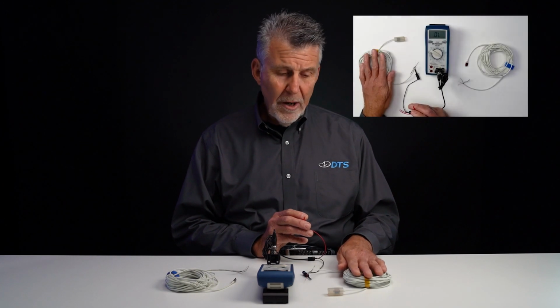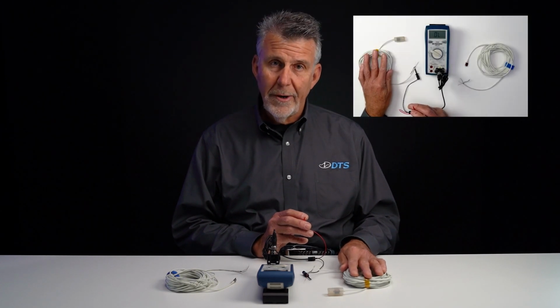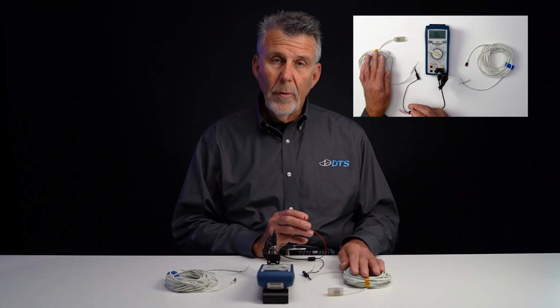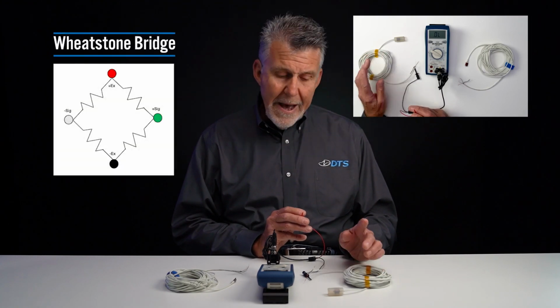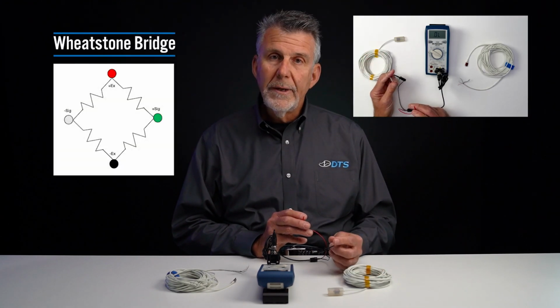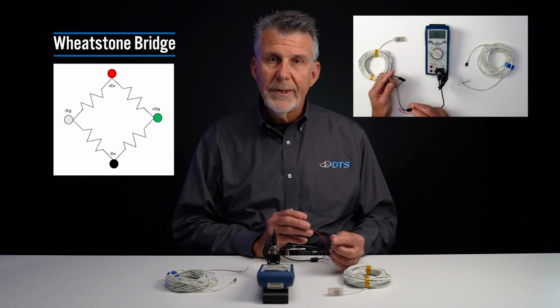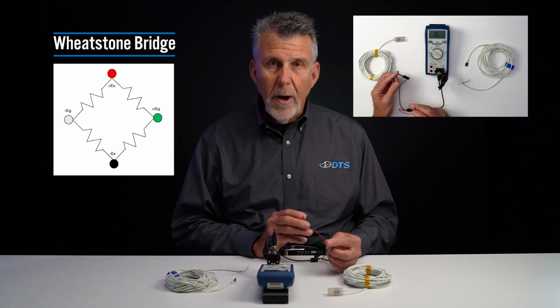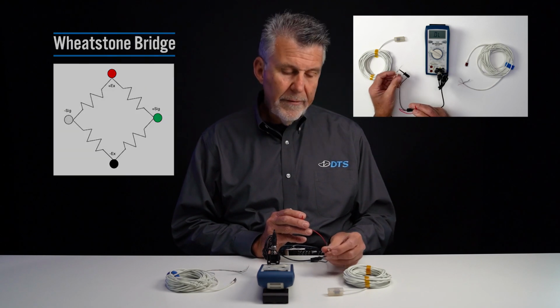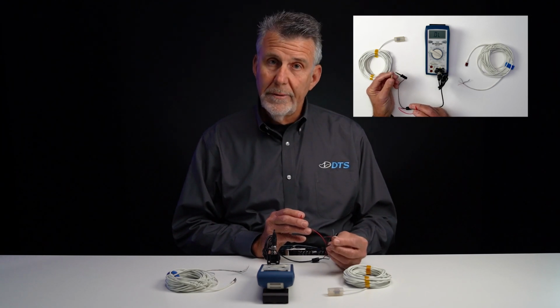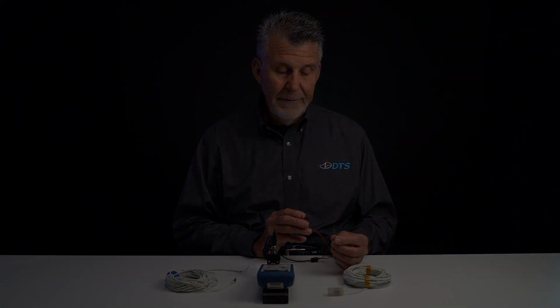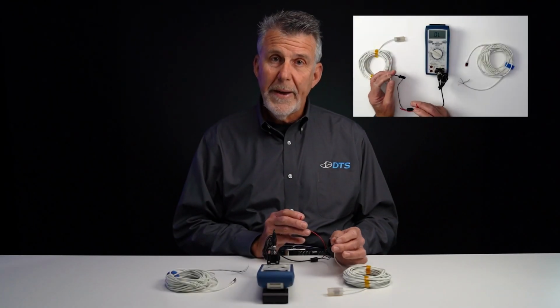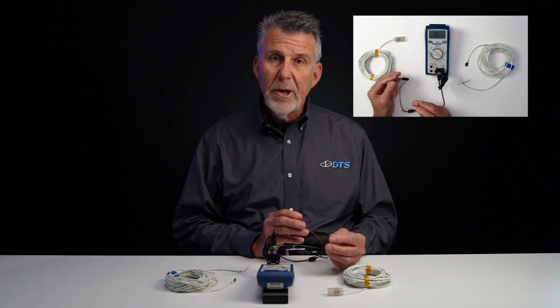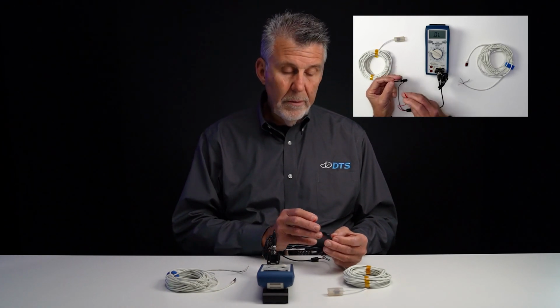Now let's check some actual sensors. Over here I have a common piezoresistive accelerometer, which is comprised of a Wheatstone bridge sensing element. That means it has 4 wires, a red and a black, which is plus and minus excitation, and a green and a white, which is plus and minus signal, and of course a shield, which is used for keeping noise out of the signals. The last time I used this sensor, it was working fine, so I don't really expect to find a problem, but I'm going to check the sensor as an example of what you should expect in a working sensor.